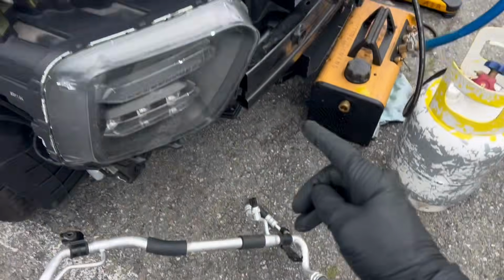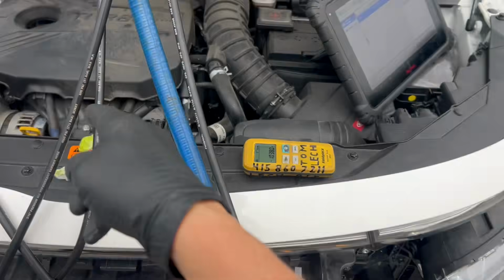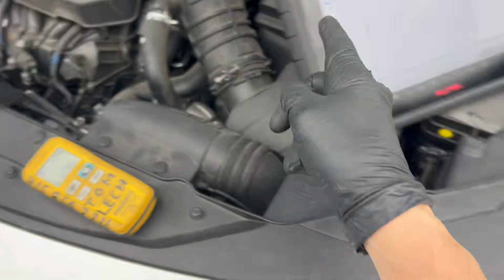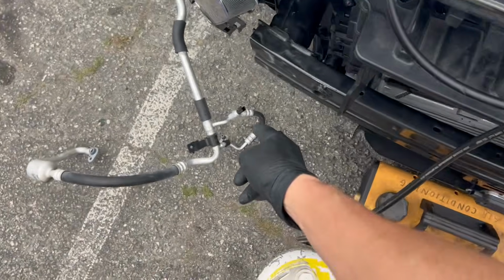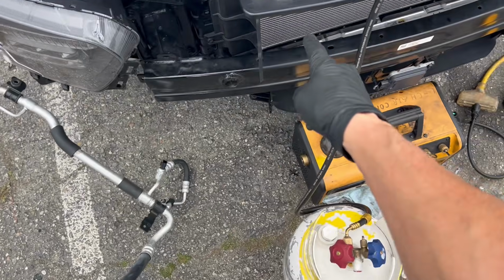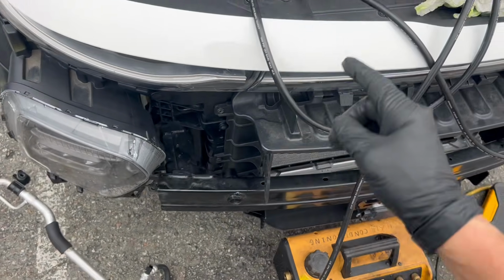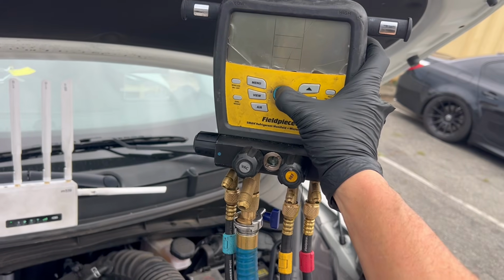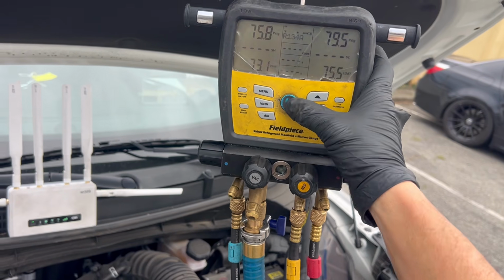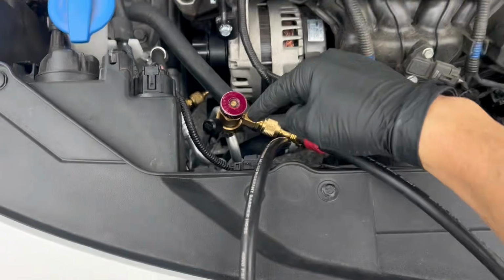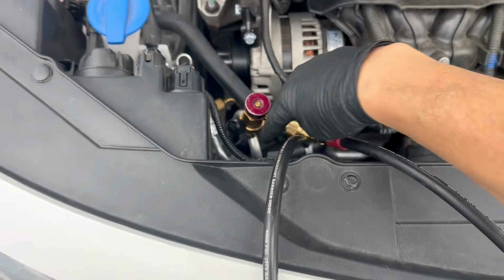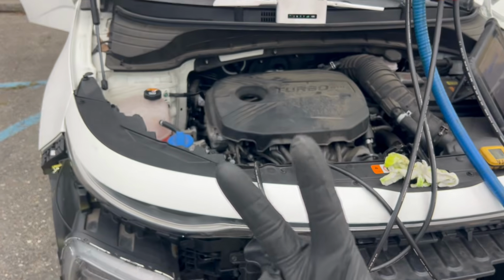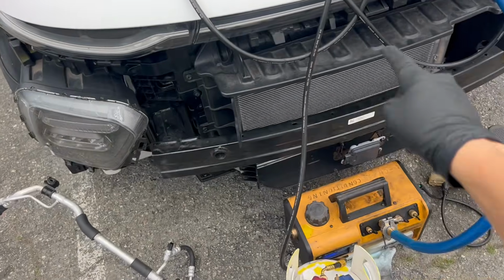Here's another one. You have your Autel. You're reading your pressure transducer. And in this one, the pressure transducer is located in the liquid line. That means after the condenser. But you have your gauges located on the high side at the compressor discharge. That means you now have two devices to take two pressure points across your condenser.